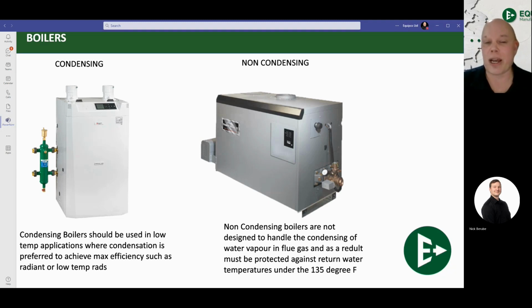The heat exchangers are designed to see condensate, which is going to be mildly acidic. It is mildly acidic because our atmosphere is about 80% nitrogen. That nitrogen, through the condensation of flue gases, turns into nitric acid. It's a mild acid, about the same as orange juice, roughly, but that's about as acidic as it is. Stainless steel heat exchangers and aluminized heat exchangers can deal with condensate all day long.